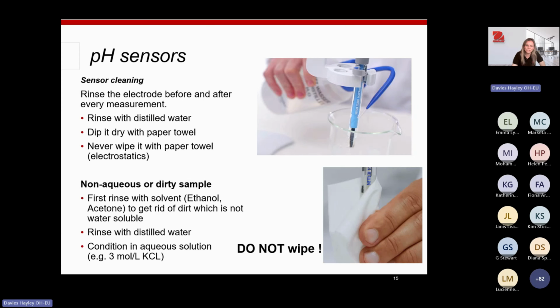For non-aqueous or dirty samples, first you can use a solvent, such as acetone or ethanol, to get rid of any dirt which isn't soluble in water. But once you do that, you should immediately rinse the solvent off with distilled water, and then you must pop it back into an aqueous solution. So condition it in your 3 molar KCl, or pop it back in your storage solution, just to make sure that any dryness that's occurred from the solvent is rectified in the solution. And again, do not wipe the probe, just dab it dry with your towel.